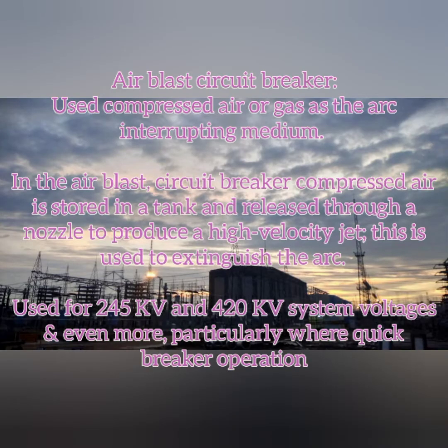Next, coming up to our air blast circuit breaker. So this air blast circuit breaker uses compressed air or a gas as the arc interrupting medium. In this air blast circuit breaker, compressed air is stored in your tank, which is at the bottom, and released through a nozzle to produce a high velocity jet. This is used in the extinction of the arc.